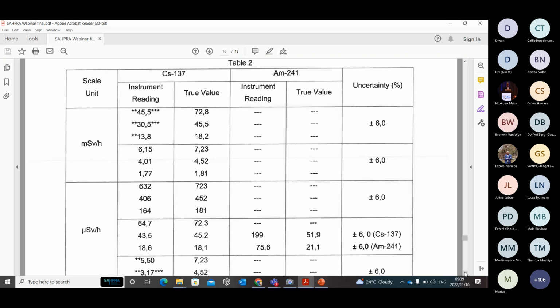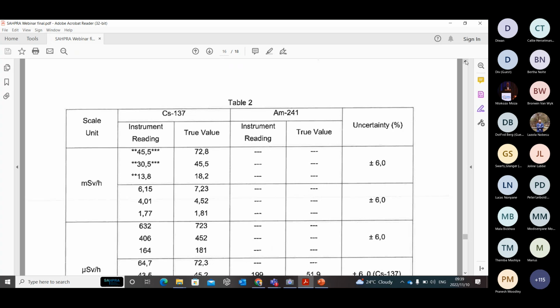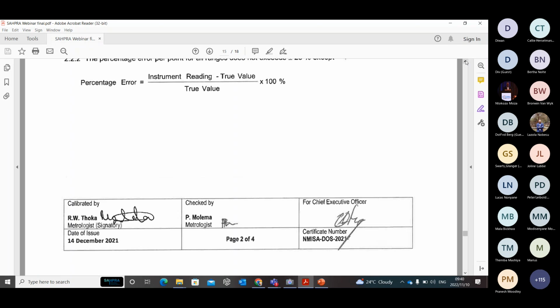As we look at this certificate, for example, if you look at range number 1, this is on 50 millisieverts. You can see that there is some form of non-conformance. Why do we have these stars? We have two requirements that our instruments have to comply with. Number one, on each point of measurement, the measurements must not exceed 25%, which means that the percentage difference between the true value and the results from the UUT should not differ by more than 25%. That's why you'll have the 3 stars.